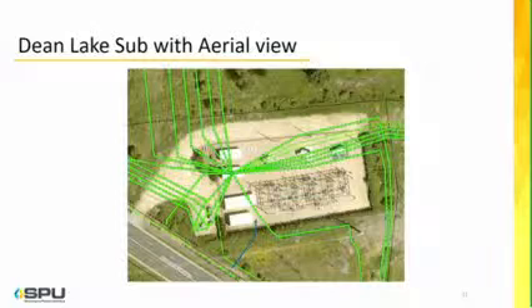This is the first switchgear building, and the second one. You can see the third one is much larger, because the interconnect that goes out west to the energy park is all run in there. Even though the lines are drawn this way, I think it's going into the larger building. This building also houses some metering and relaying equipment for Xcel Energy, because this is one of those subs that has all the breaker positions filled now on the bus, and this is more automatic to switch should there be an outage in one direction or the other.